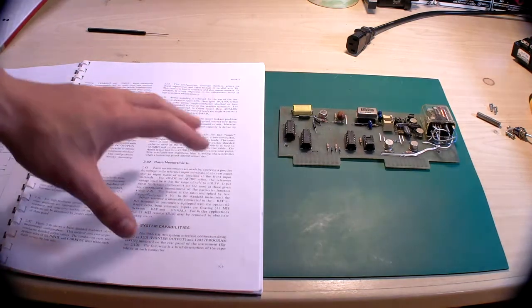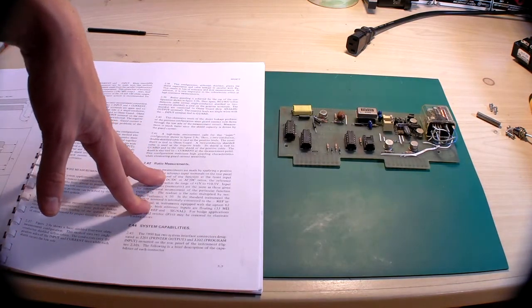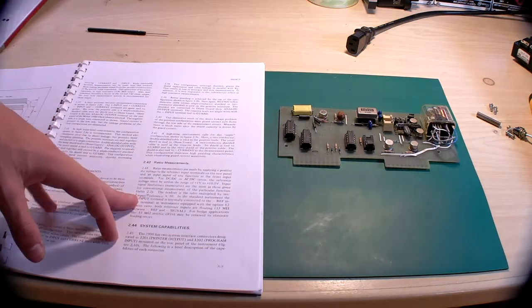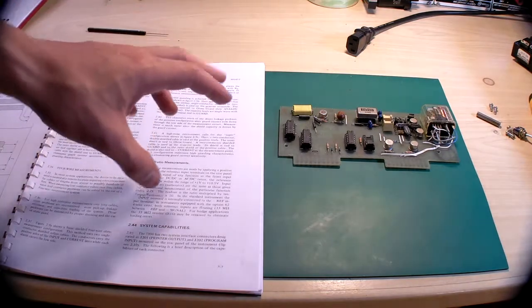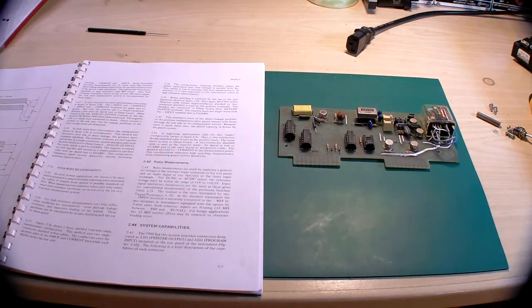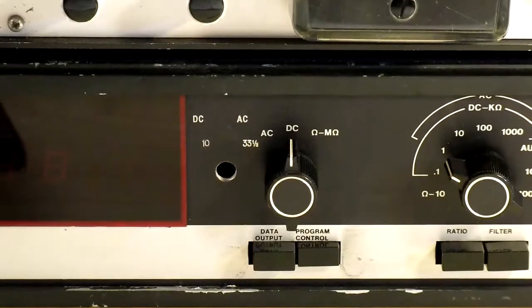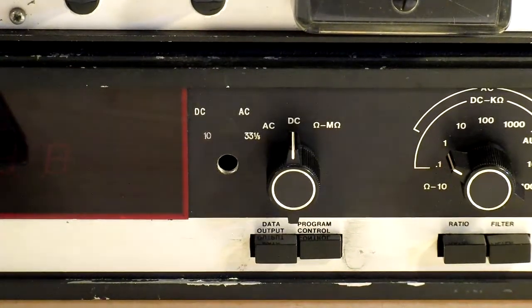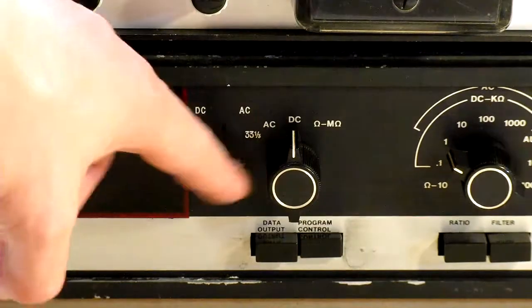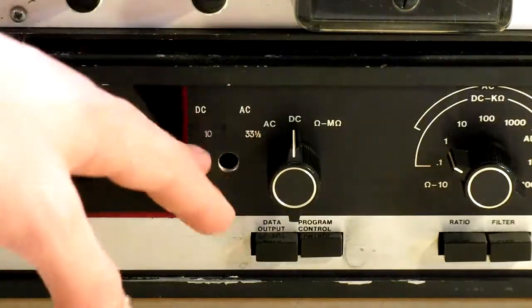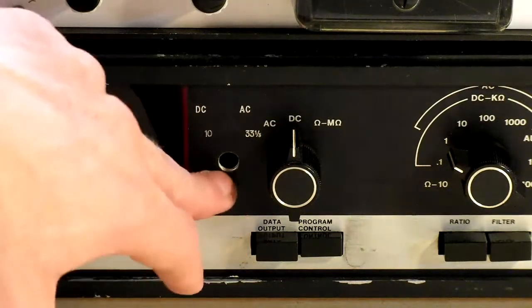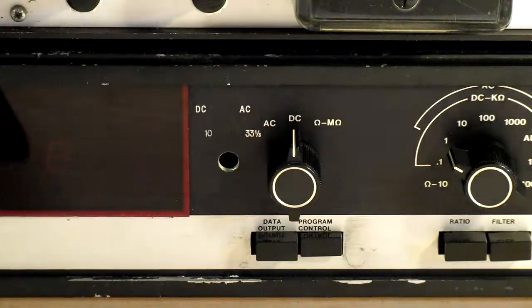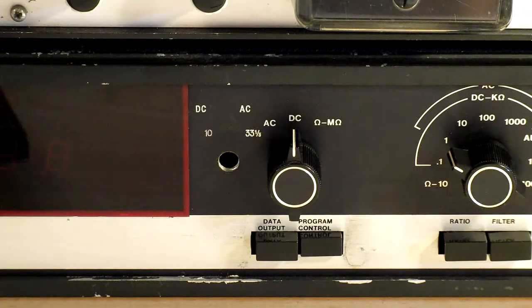What's interesting is that someone modified this to not only multiply by 10, but also by 33 and a third. You can see here where the actual switch was, letting you switch from the times-10 multiplication to times-33⅓. So your 4-wire ratio was input over reference times 10, or times 33⅓.